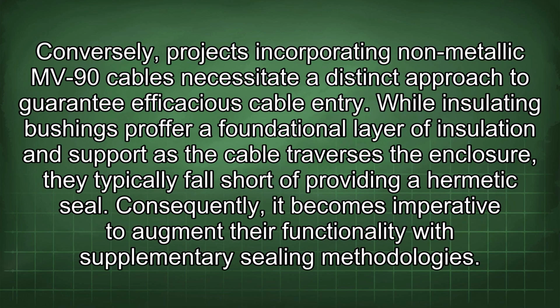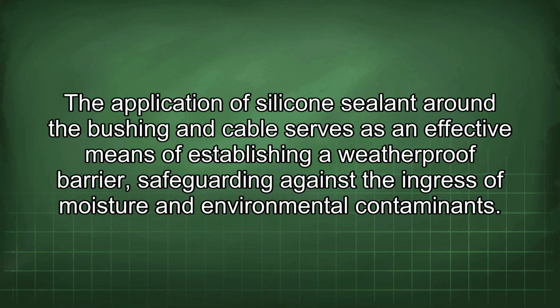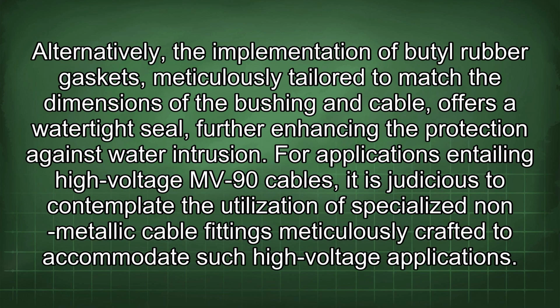Conversely, projects incorporating non-metallic MV-90 cables necessitate a distinct approach to guarantee efficacious cable entry. While insulating bushings proffer a foundational layer of insulation and support as the cable traverses the enclosure, they typically fall short of providing a hermetic seal. Consequently, it becomes imperative to augment their functionality with supplementary sealing methodologies. The application of silicone sealant around the bushing and cable serves as an effective means of establishing a weatherproof barrier, safeguarding against the ingress of moisture and environmental contaminants. Alternatively, the implementation of butyl rubber gaskets meticulously tailored to match the dimensions of the bushing and cable offers a watertight seal, further enhancing the protection against water intrusion.